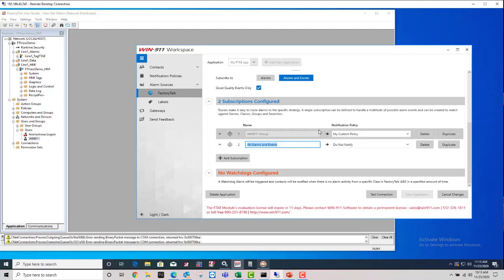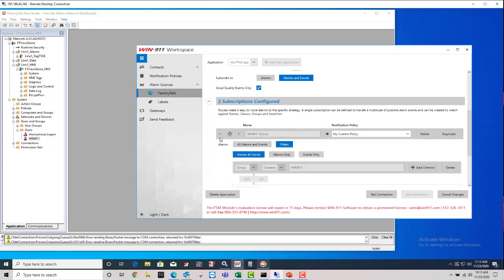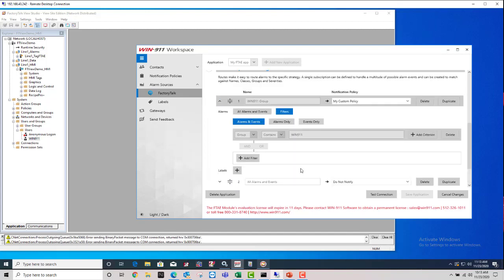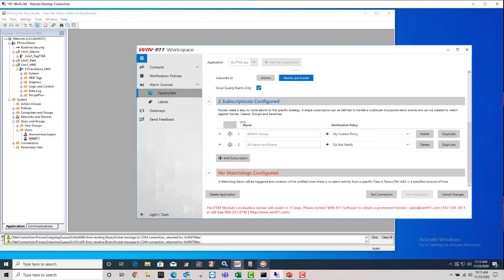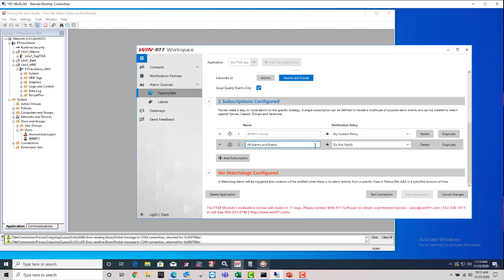All alarm and events are going to go to do not notify. And you'll see that in the log viewer. And then you might have to tweak the filter you've created, come back in here, and if you were using wildcard, maybe change to just contains or change where your wildcard is. But that's just a good testing rule of thumb in the beginning here, make that extra line as a catch-all.